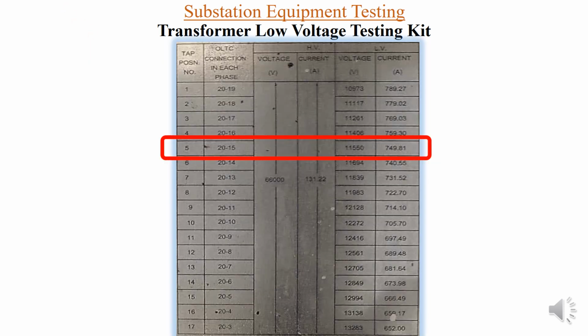Friends, this is the nameplate detail of the transformer. As you can see, on the HV side the voltage is 66,000, that is 66 kV, and on the LV side for different steps from 1 to 17, it is increasing in this manner. We have obtained a similar kind of result in the voltage ratio test that we conducted. One thing to observe over here is that at step number 5, when the HV side voltage is 66 kV, the voltage you are getting on the LV side is 11.55 kV. So this is the normal operation step of this transformer, because at step number 5 you are getting the complete output of 66 by 11.5 kV.